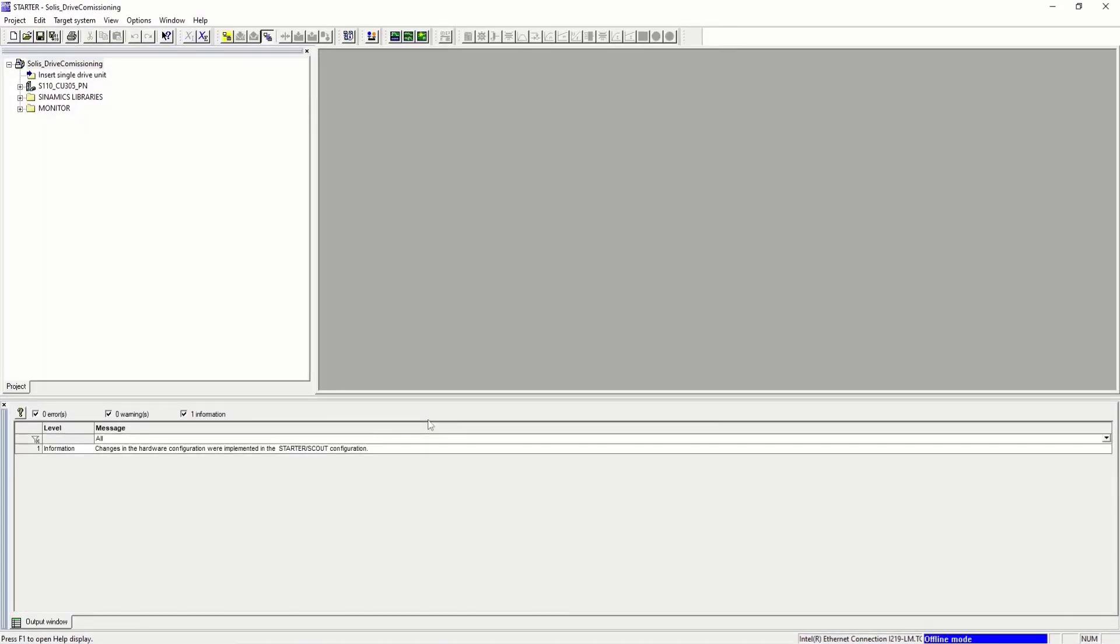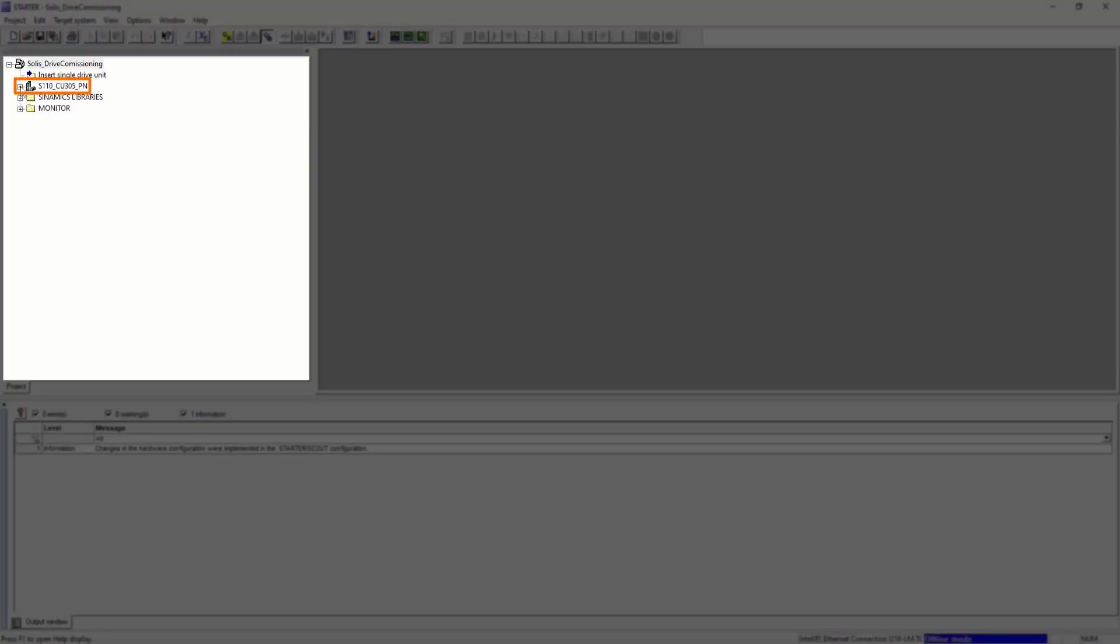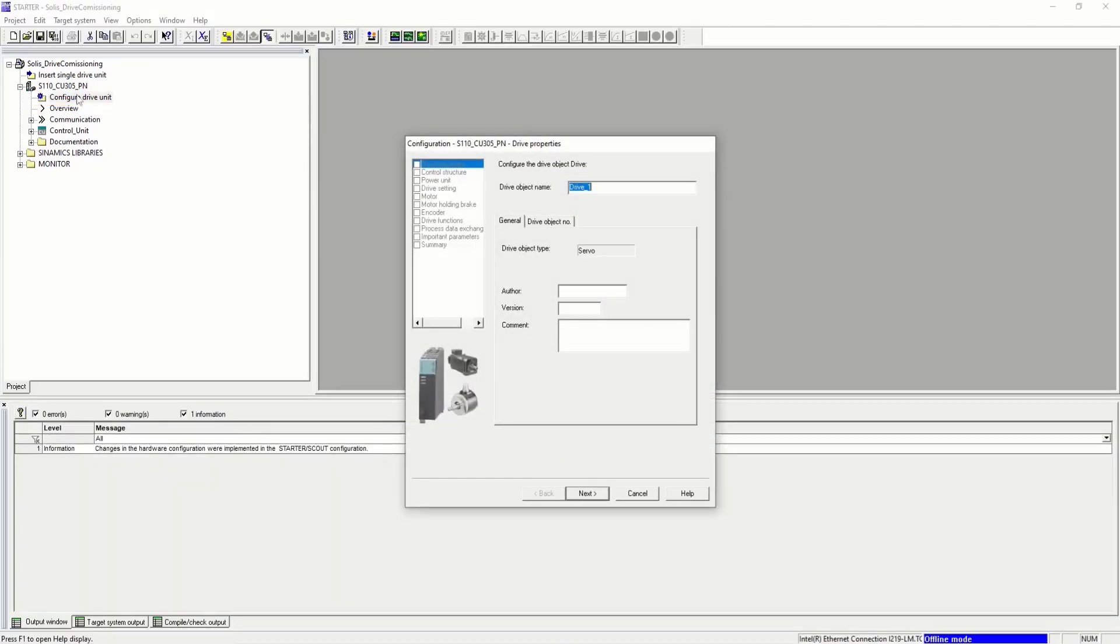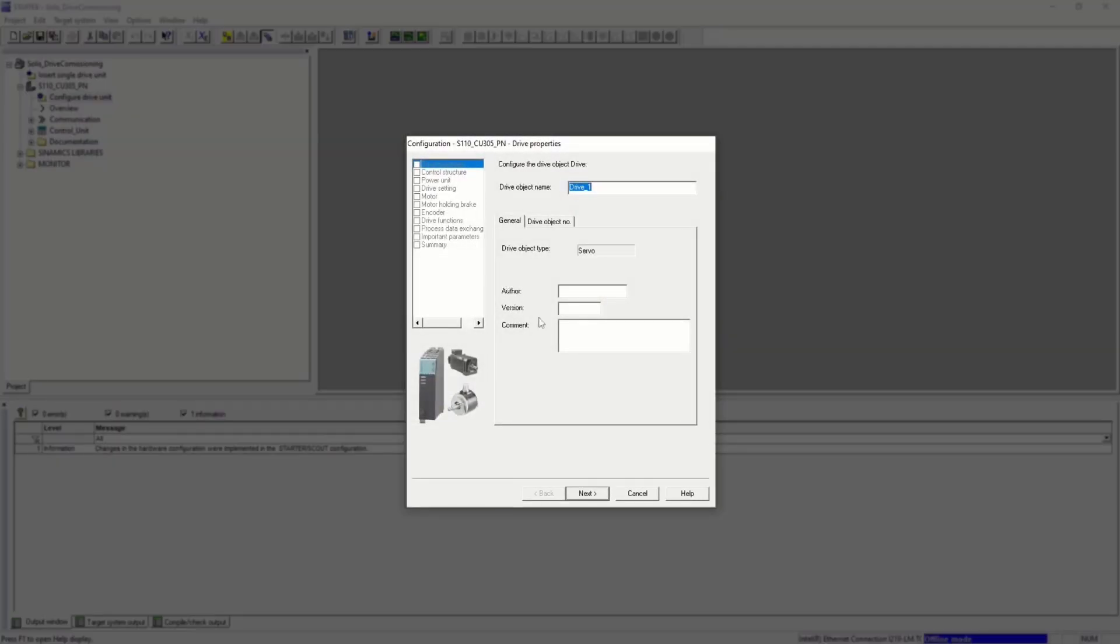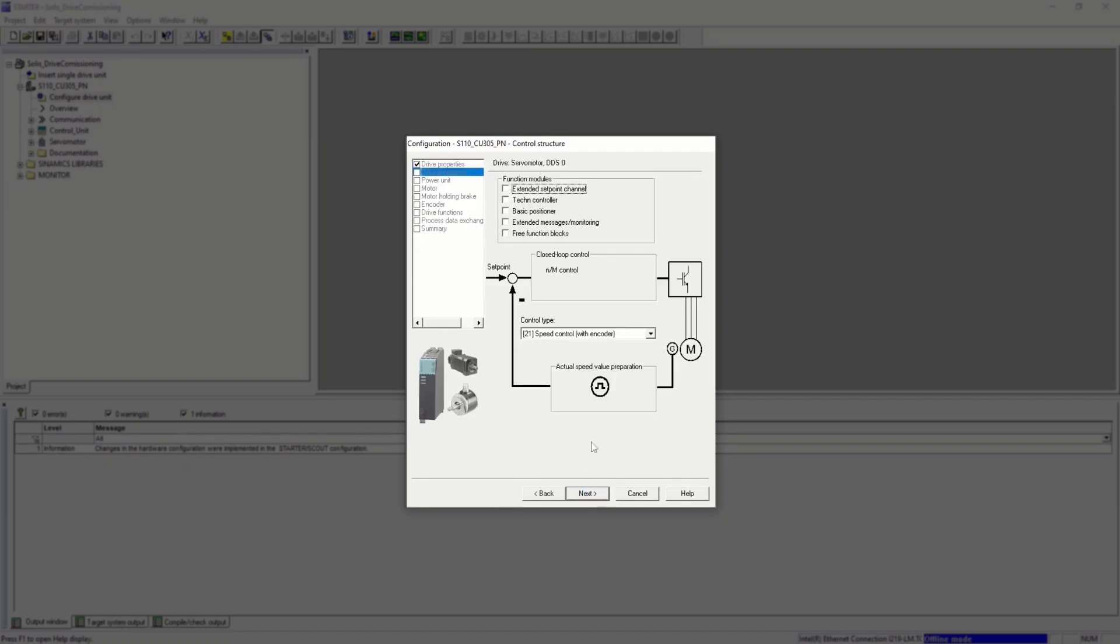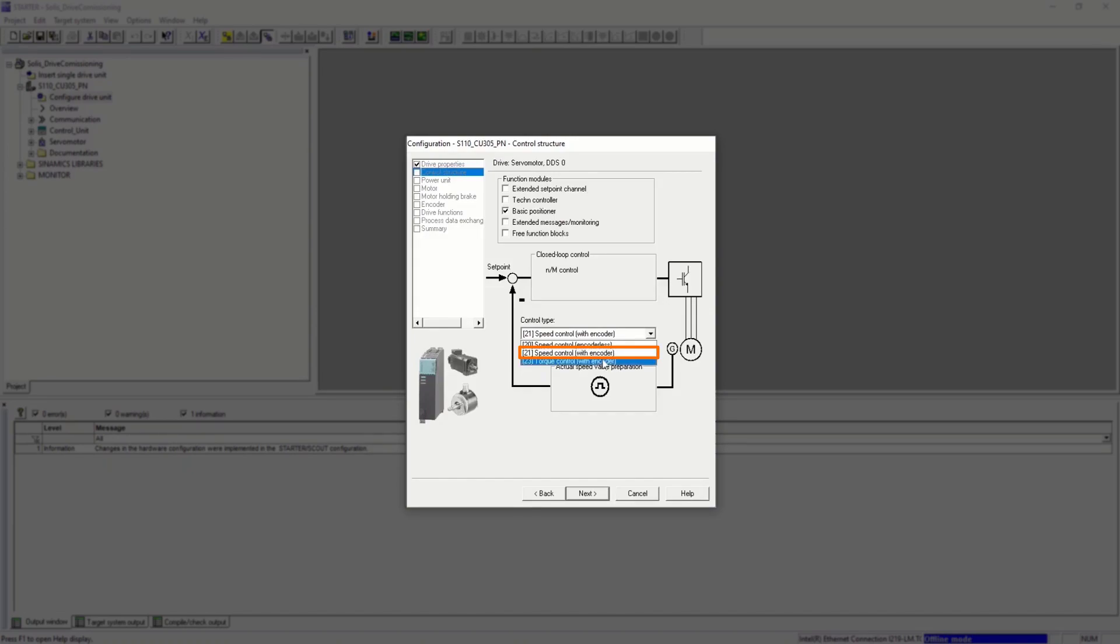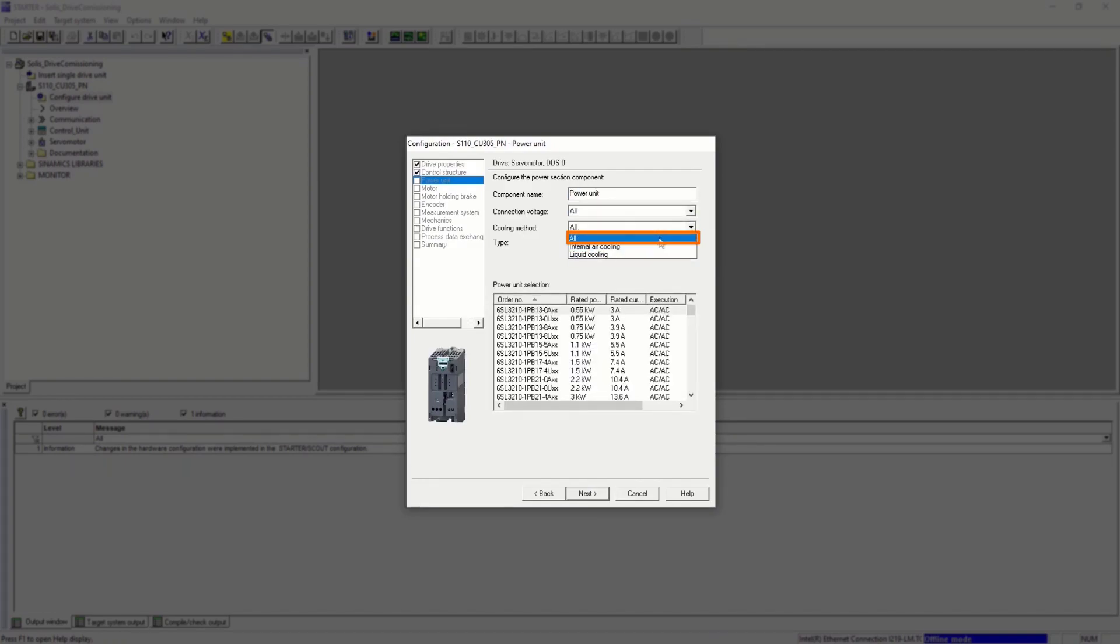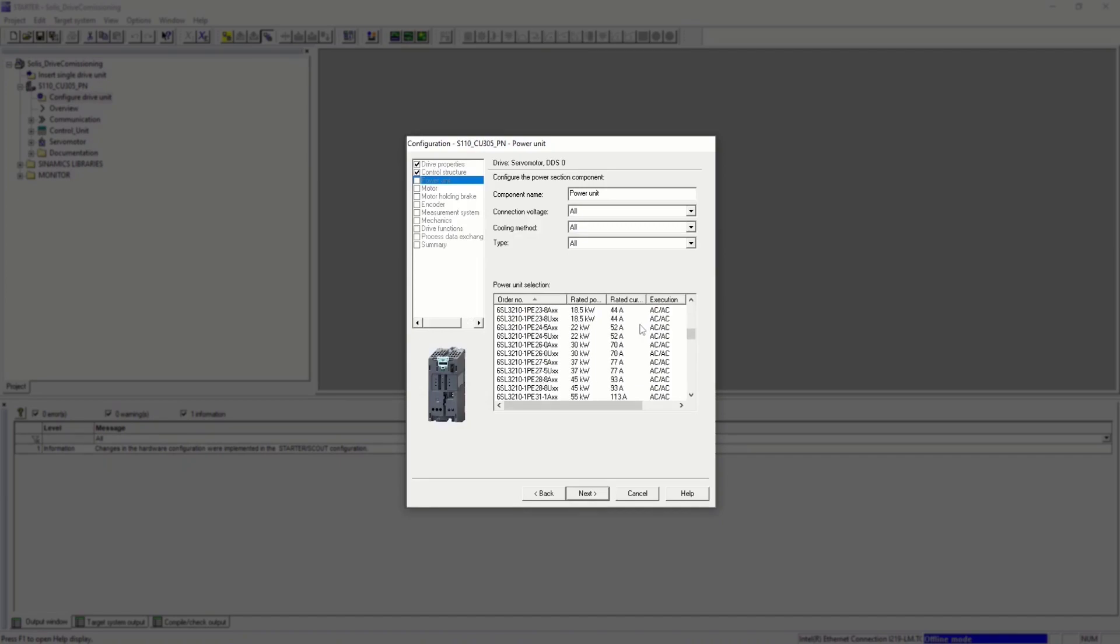Let's configure the drive unit. Choose an identity name for the drive. For the control mode, we're going to use the basic positioner function module and the speed controller with encoder control mode. Find the correct power unit for your device. Make sure the correct filters are selected.